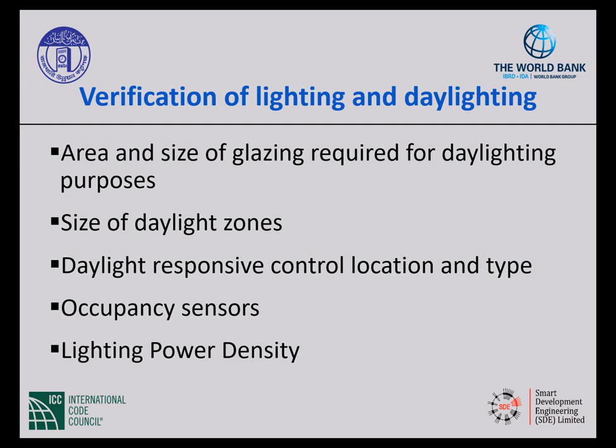Not asking inspectors to go out in the field and count light bulbs to make sure that they're meeting their lighting power density. But a lot of times what I will do as an inspector is do spot checks. I'll go into a room and maybe look at the lighting and see, do they have the right lighting? And if so, I'm not checking every single light bulb in the building. But if I start seeing that they're off in 1 or 2 rooms, then I'm going to say, okay, I'm halting this inspection. I'm seeing that your lighting is not complying, and we need to get some compliance out of this lighting. And so you can often do spot checks without looking at every single light bulb in the building.